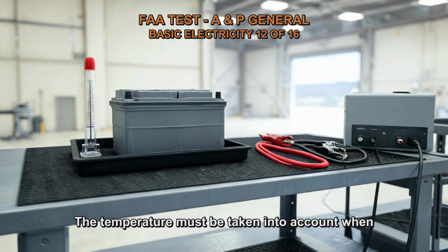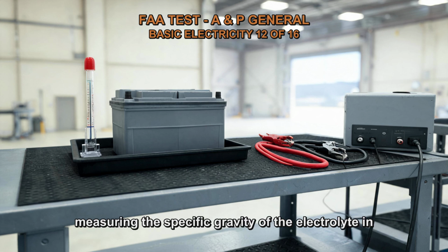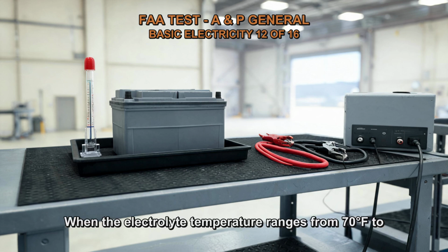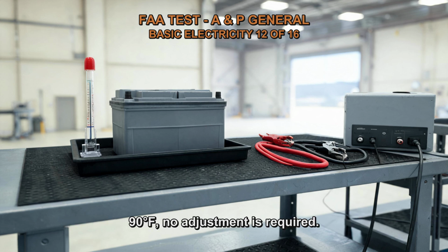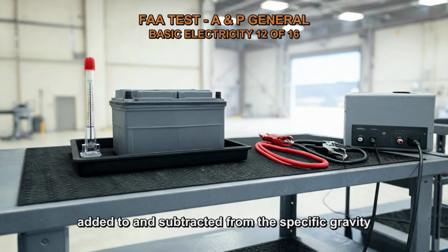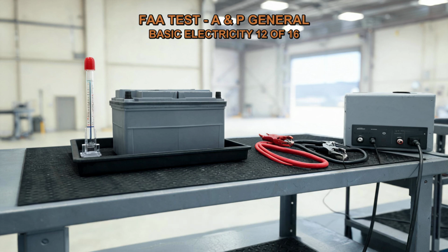The temperature must be taken into account when measuring the specific gravity of the electrolyte in a lead-acid battery. When the electrolyte temperature ranges from 70 degrees Fahrenheit to 90 degrees Fahrenheit, no adjustment is required. For every 10 degrees above 80°F and every 10 below 80°F, a correction of 0.004 should be added to and subtracted from the specific gravity result, respectively.